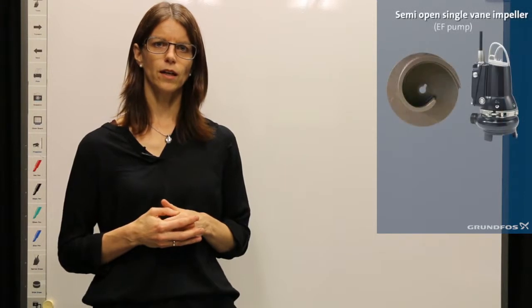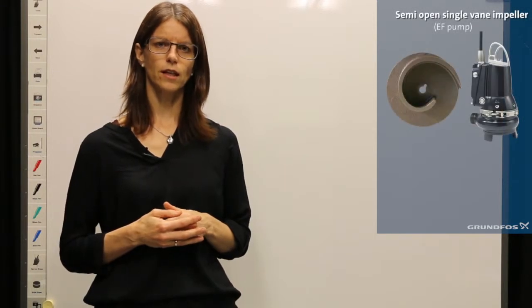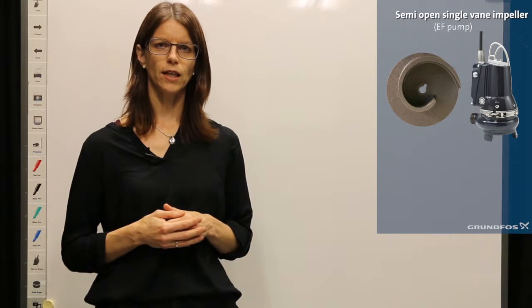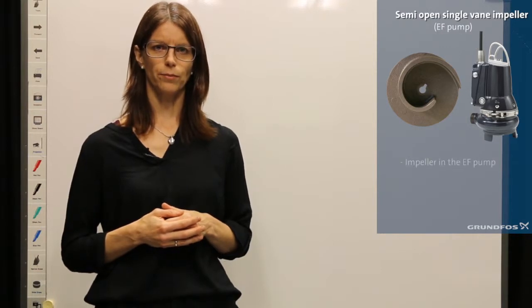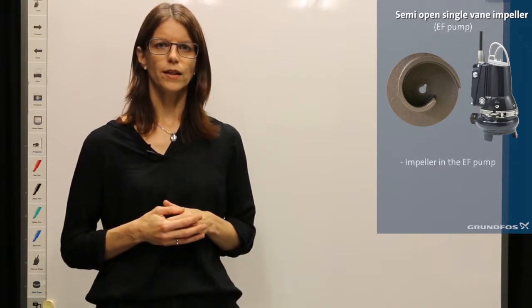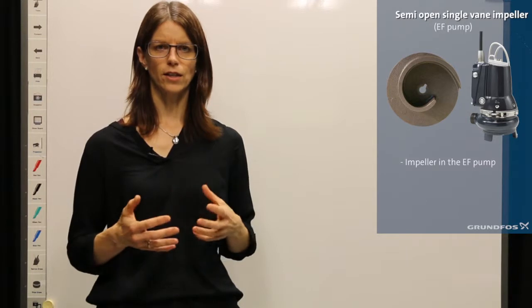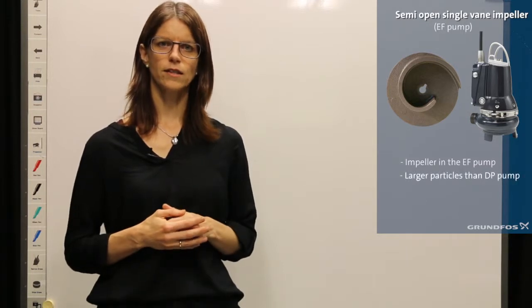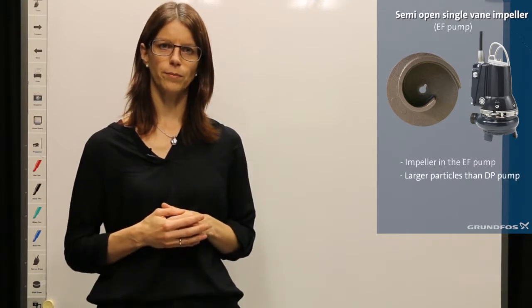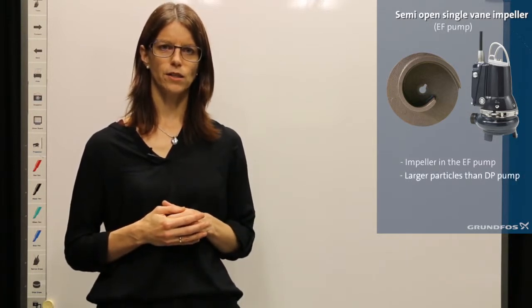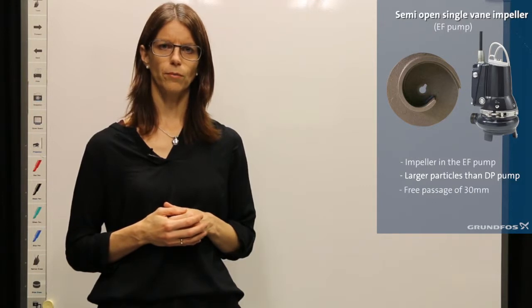Then we have the semi-open single vane impeller. This is the impeller in the EF pump. This pump can handle a little bit larger particles than the DP pump, and it has a free passage of up to 30 millimeters.